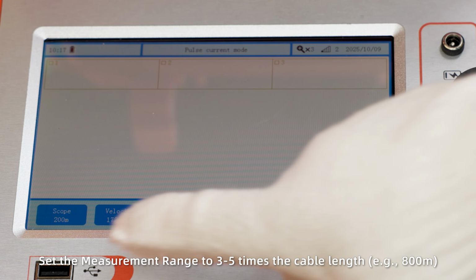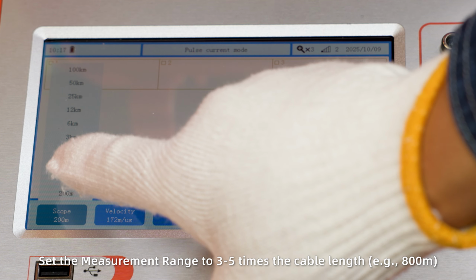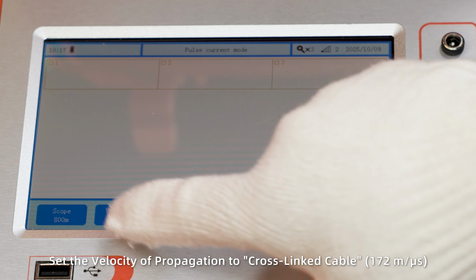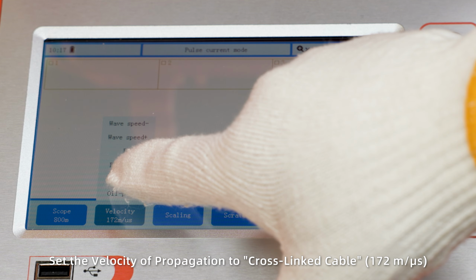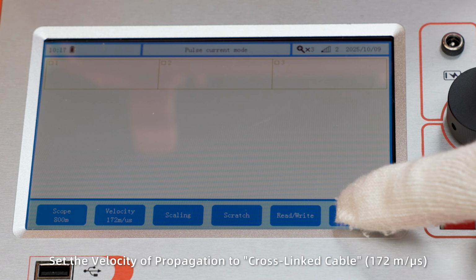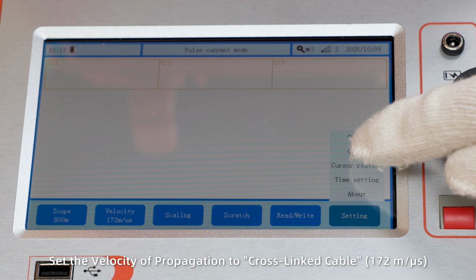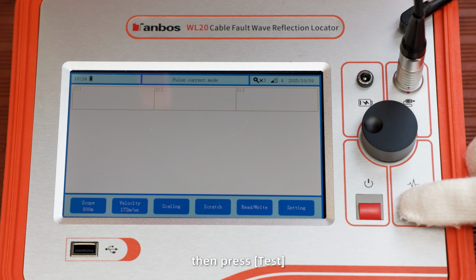Set the measurement range to 3 to 5 times the cable length. Set the velocity of propagation to cross-linked cable, 172 meters per microsecond. Set the gain to level 3 to 5, then press Test.